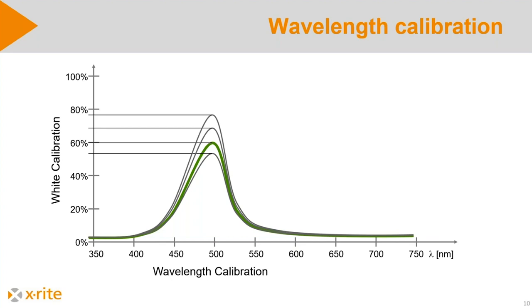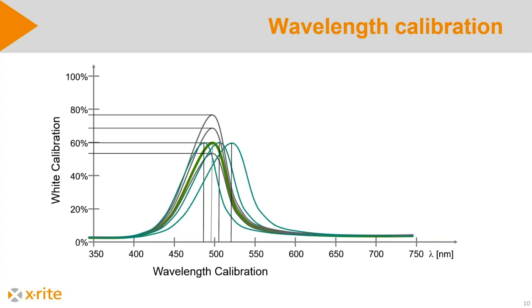But another question is, if you do the wavelength calibration, is this peak really at, in my case, 490 nanometers? Or is it maybe over here or over there? Where is this peak? This can only be determined when you do a wavelength calibration, and this can be done only with 1 nanometer resolution. That means if the instrument is on the machine and is somehow shaken or moved, the measurements will change a little bit. But after each calibration, it will be brought back to zero because we do a white calibration and a wavelength calibration at the same time.